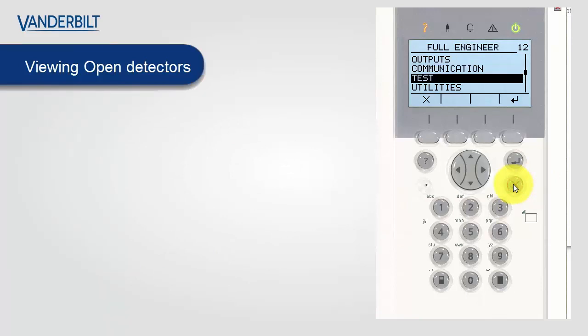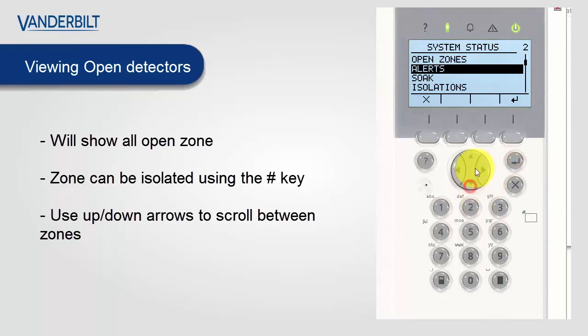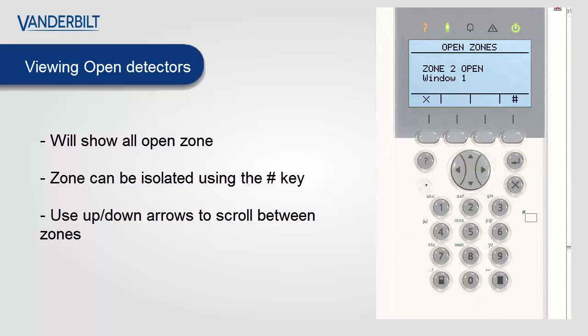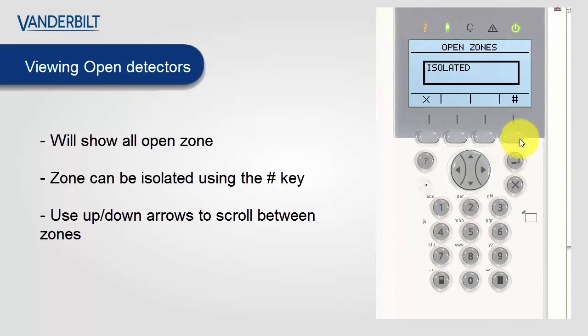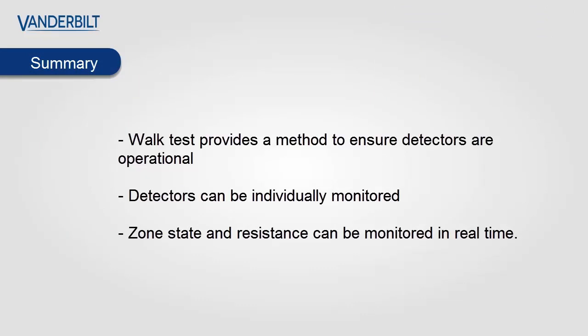Finally let's look at how to monitor for any open zones on the system. We can do this from soft or full engineer — we select system status and select open zones. This will show all open zones in the system and zones can be isolated by pushing the hash key. In summary, walk test provides a method to ensure detectors are operational. Detectors on the system can be individually monitored and zone state and resistance can be monitored in real time. We hope this helps you with your installation of SPC systems and can improve system quality and performance for end customers. Thank you for watching and goodbye.